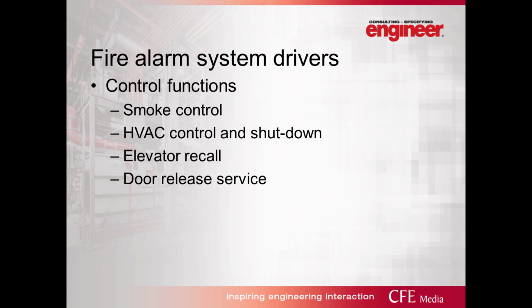So that could be driven by a fire alarm system, or it could be direct connected to the panels as well if you don't otherwise have a fire alarm system. We also have elevator recall. So every elevator that extends more than one story now is required to have a recall. So if you do put a panel in just for recall, NFPA 72 would classify that panel as a dedicated fire alarm panel, and additional fire alarm devices would not be required.